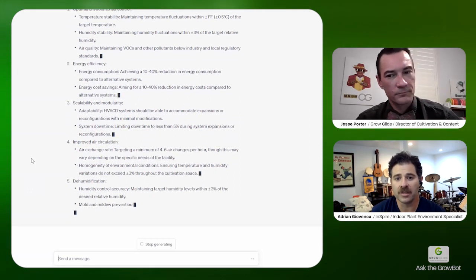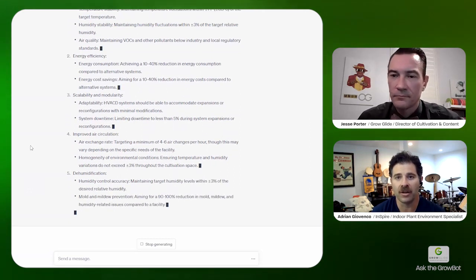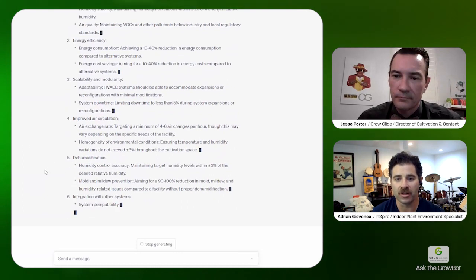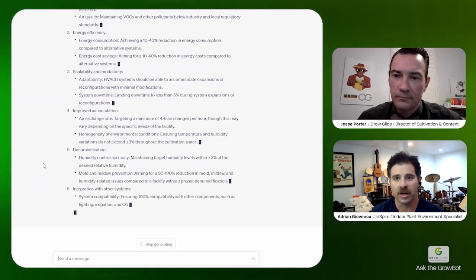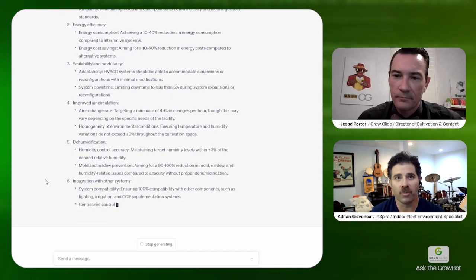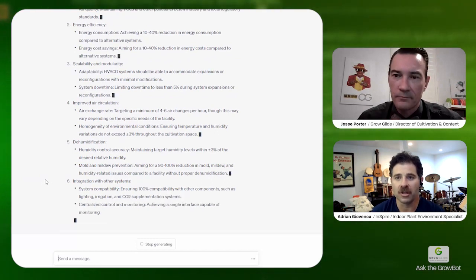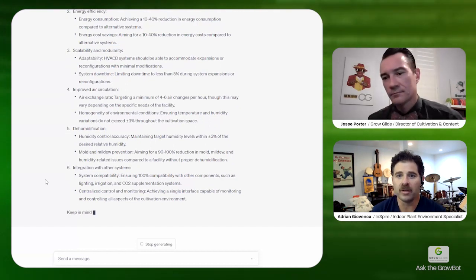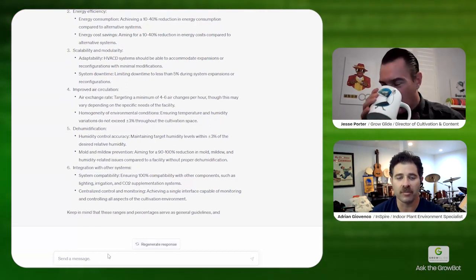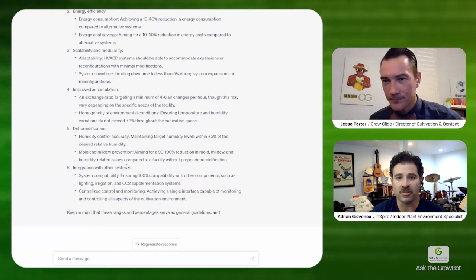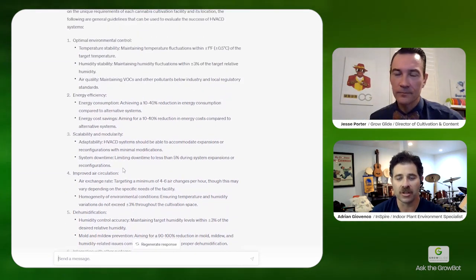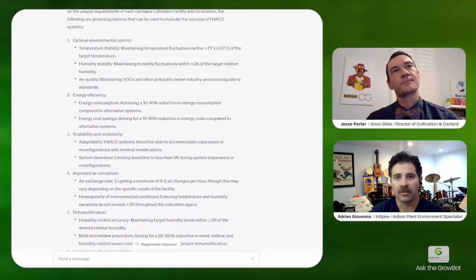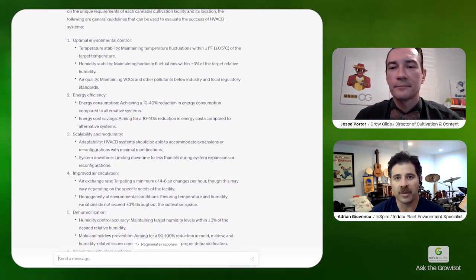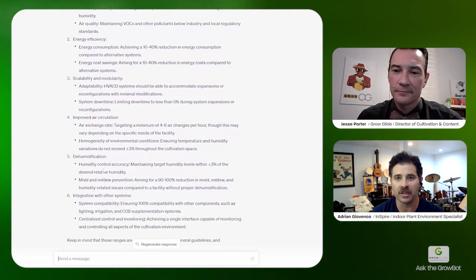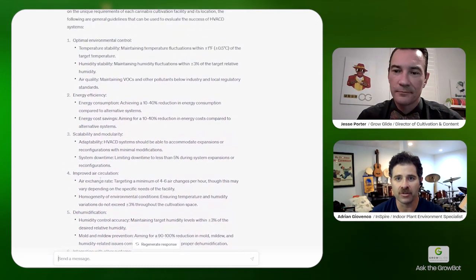Yeah, the redundancy piece is really important, figuring out what that means to a cultivator and to the business itself. There's different ways you can look at it. You can say, okay, if I put one purpose-built system in there, I'm banking on that unit being up in order to make sure I've got my condition. But if you look at uptime on a piece of equipment like that, call it 95 to 99% of the hours of the year, there's going to be some downtime for maintenance or repairs.